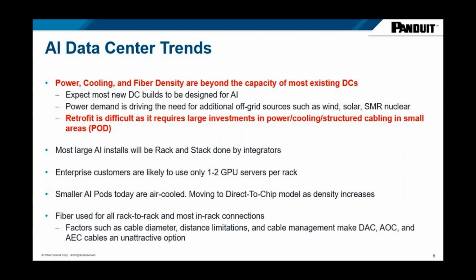Lastly, fiber is used for all rack-to-rack and most in-rack connections. Factors such as cable diameter, distance limitations, and cable management make direct attached copper, active optical, and AEC cables an unattractive option, so you'll see fiber predominantly used in AI connectivity. We're seeing customers using direct attach options having issues with cable management due to cable rigidity and the diameter of the cabling itself.